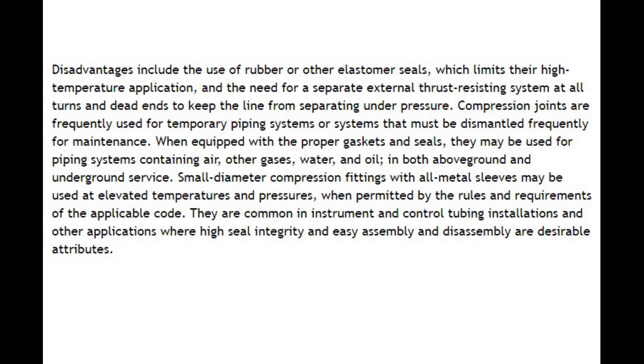Disadvantages include the use of rubber or other elastomer seals, which limits their high temperature application, and the need for a separate external thrust resisting system at all turns and dead ends to keep the line from separating under pressure. Compression joints are frequently used for temporary piping systems or systems that must be dismantled frequently for maintenance. When equipped with the proper gaskets and seals, they may be used for piping systems containing air, other gases, water, and oil in both above ground and underground service.